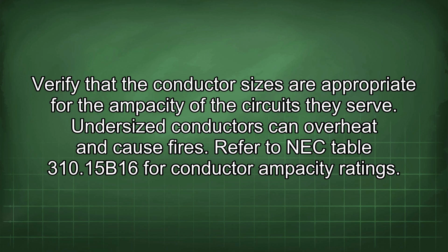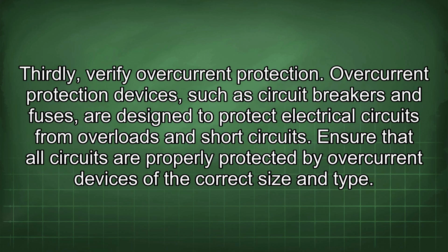Refer to NEC Table 310.15(B)(16) for conductor ampacity ratings. Thirdly, verify overcurrent protection. Overcurrent protection devices, such as circuit breakers and fuses, are designed to protect electrical circuits from overloads and short circuits.